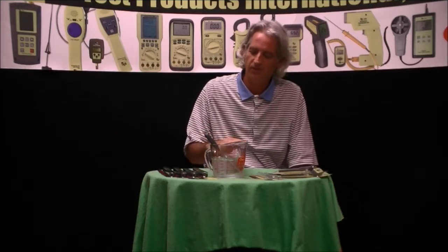degrees. There's a nice feature on these units in the auto cal mode. If it doesn't sense 40 degrees Fahrenheit or less, it won't calibrate your unit, so you know you can't screw these things up. If it doesn't hold the calibration, it'll just flash error at you after you've done the cal, and it'll revert back to the last calibration that was done.